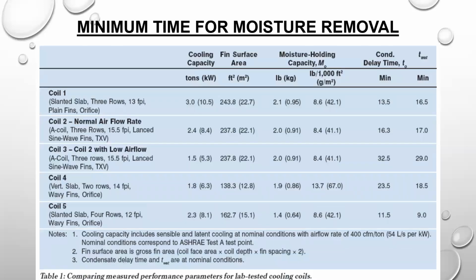If you'll notice, coil number 2 is what I consider a normal coil for HVAC equipment. That takes a minimum of 16.3 minutes for that moisture to build up on the coil, get down to the drain pan, and get out. So I always tell everybody you need at least a minimum 15-minute runtime to do any dehumidification. Anytime it shuts off before that time, nothing's done. You just wasted all that energy. The RCCD device will actually do a little bit to improve your efficiency of your unit, and that's discussed in great detail on other presentations.